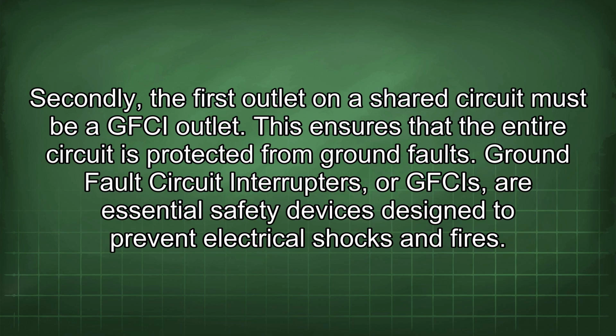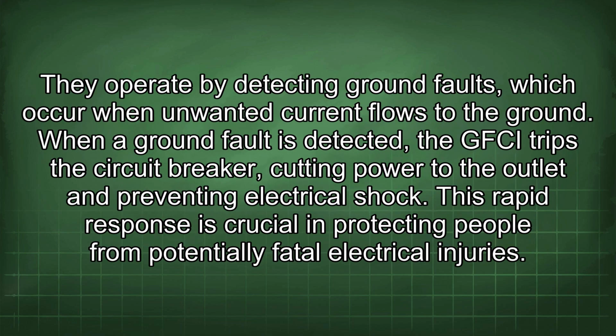Ground fault circuit interrupters, or GFCIs, are essential safety devices designed to prevent electrical shocks and fires. They operate by detecting ground faults, which occur when unwanted current flows to the ground. When a ground fault is detected, the GFCI trips the circuit breaker, cutting power to the outlet and preventing electrical shock. This rapid response is crucial in protecting people from potentially fatal electrical injuries.